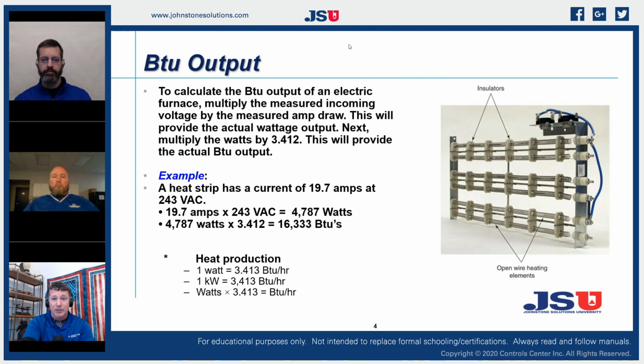If Greg Millsaps was on here, I probably wouldn't be able to talk right now. He would be running with this show because he's so passionate about understanding airflow in electric furnaces, because we overlook that so many times. If we were working on a gas furnace and we're doing a tune-up on it, we're going to check temperature rise, right? We don't always do that with an electric furnace. We assume that some of our variables are constant, and they're not. We have things that change, and so we need to understand what those changes are.